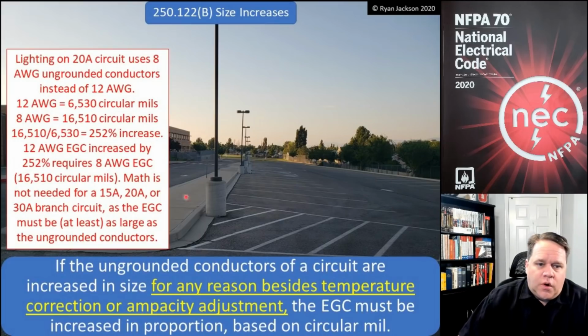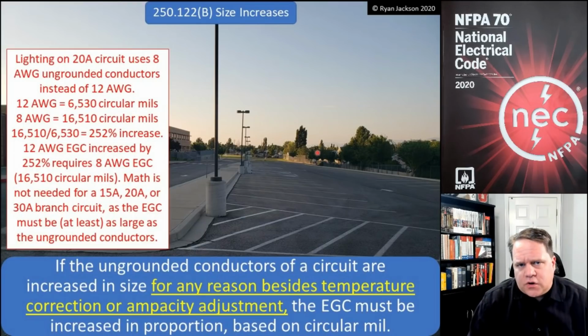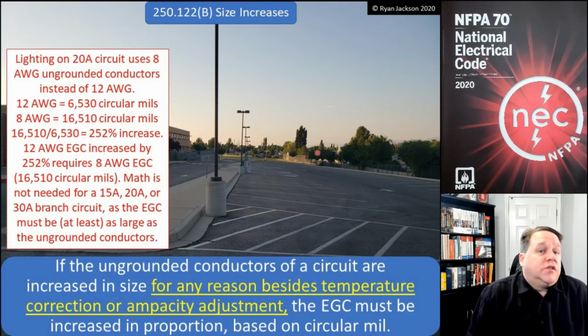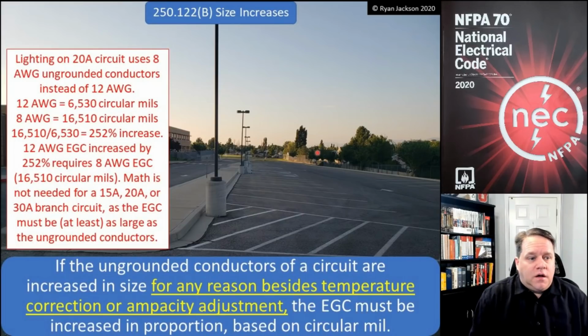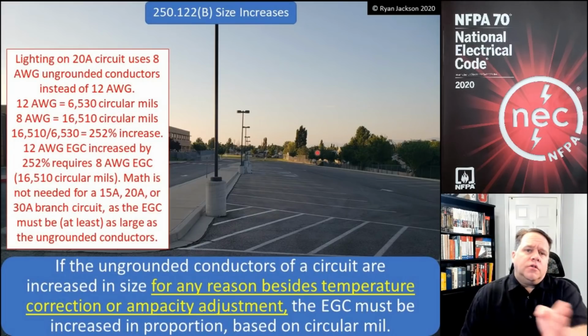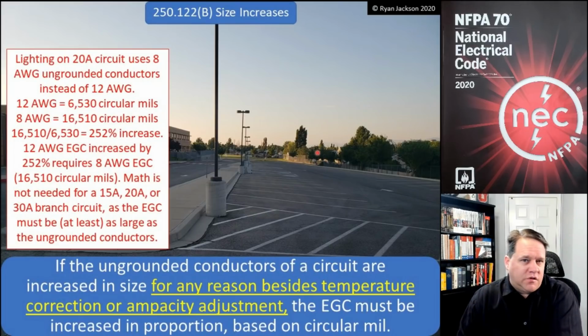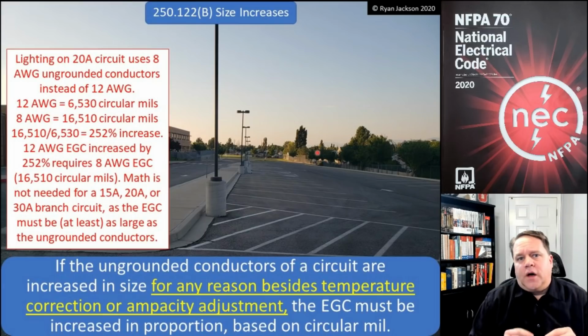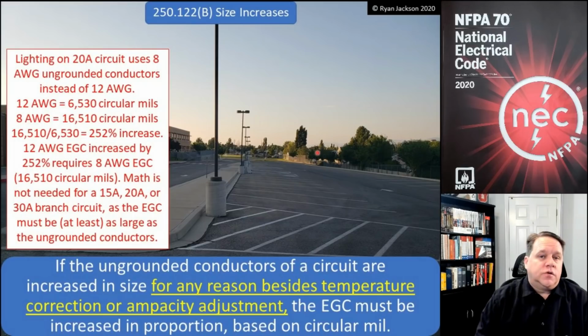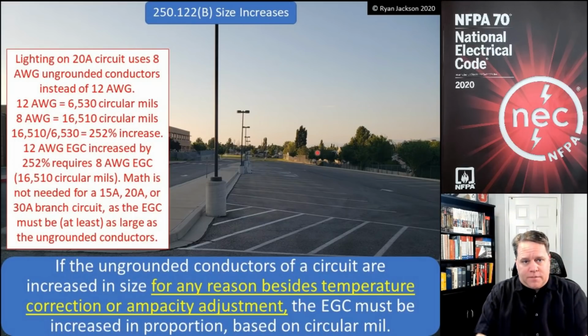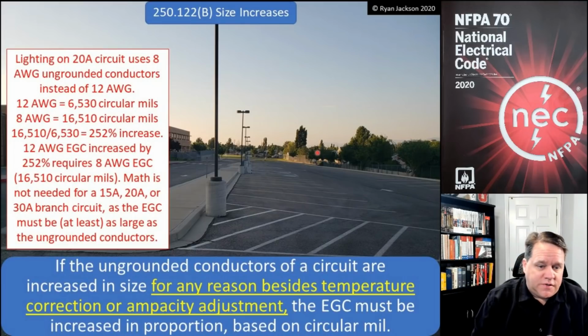All right, so I'm showing a parking lot here in the picture, and the reason that I'm doing that is, why would I increase the size of ungrounded conductors? Well, usually it's a voltage drop issue. And in fact, in 1975, when they put it into the code, all the way up to, I believe, 2002, it said that this only applies when you're increasing the size of your wire for voltage drop. And in reality, that's the most common application of this rule. So I want to just stick to voltage drop for right now. I've got a parking lot. It's got a long circuit. I increased the size of my conductors. That means I have to increase the size of my equipment ground in proportion, right? That's what this rule says.